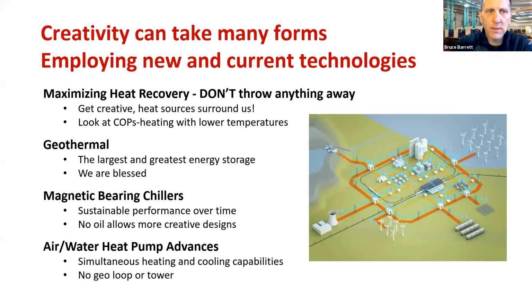So the 4 topics we're going to talk about today are employing some recent or new developments in technology, some old technologies that are trustworthy, tried and true, and they work very well, like geothermal, applying magnetic bearing chiller technology, making hot water using the mag bearing product, and then advancements in air-to-water heat pumps and how they have evolved to deliver both warmer temperatures and extract heat, additive compression with new compressor technology at very cold ambience.